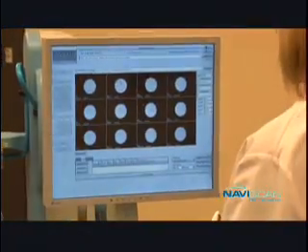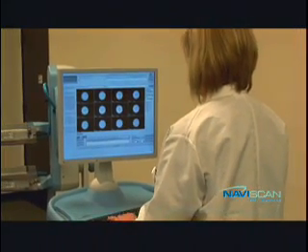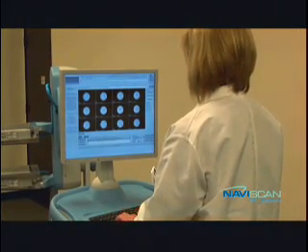The close proximity of the crystal detectors and limited-angle tomographic reconstruction results in an in-plane spatial resolution of 1.5 mm, compared to the 4.2 to 6.5 mm axial resolution found in commercially available whole-body PET scanners.